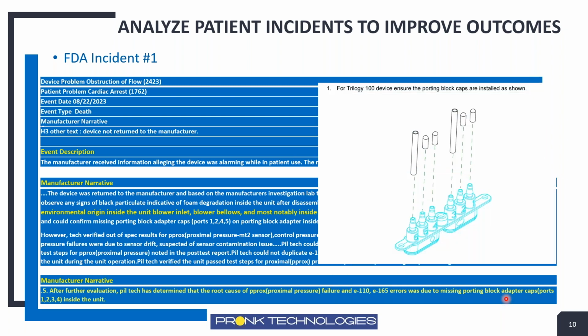They concluded that the root cause of this failure was due to missing porting block adapter caps. This particular ventilator requires you to install porting block adapter caps in a particular configuration. And because these caps were not installed, unfortunately, ingress of debris got into the ventilator and caused the problem. So this is just an example of some issues that can happen and why it's important that we make sure we don't miss any steps when we're out there servicing ventilators, because some of these steps can be very, very critical in the performance of the device.